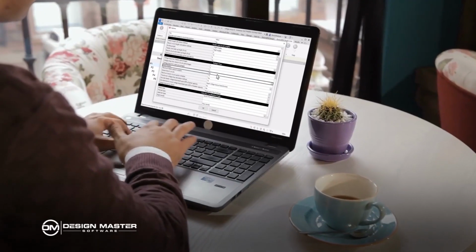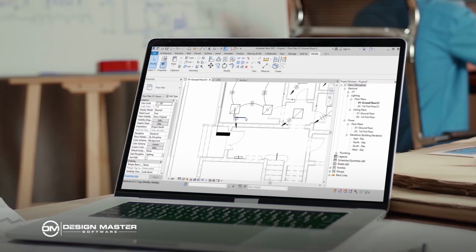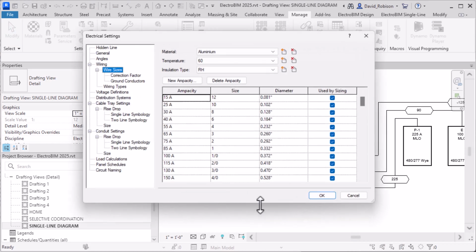As long as I've been working with Revit, it has had voltage drop as a feature, and in the entirety of that time, it has never changed, and it has always been just a little bit broken. It has wire lengths built into it, but these wire lengths are not well calculated, and they're not something that most engineers are comfortable using. The wire sizes were always limited to copper wires for their impedances, so your voltage drop only worked on copper wires, it didn't work on aluminum.